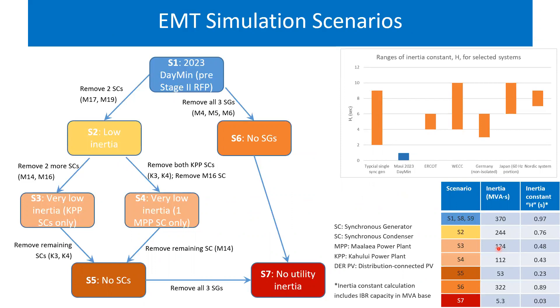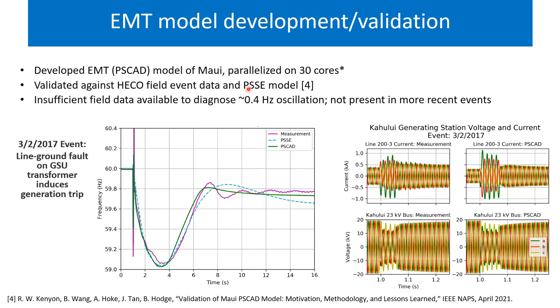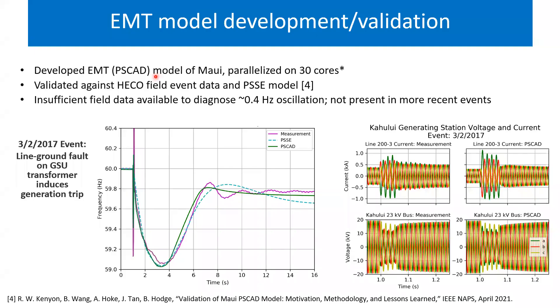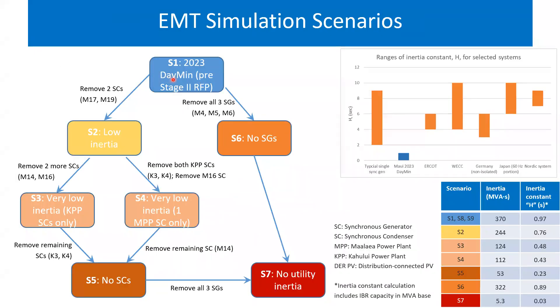We can see a pretty good match between field data and EMT simulation — obviously not perfect, but close enough to have a good representation in PSCAD. We then used that model to run EMT simulations starting from scenario one, the DayMin dispatch case, developing additional scenarios by basically starting to take off synchronous generators and synchronous condensers.